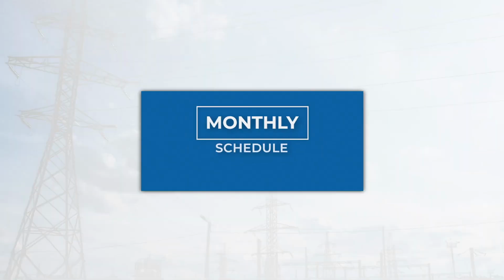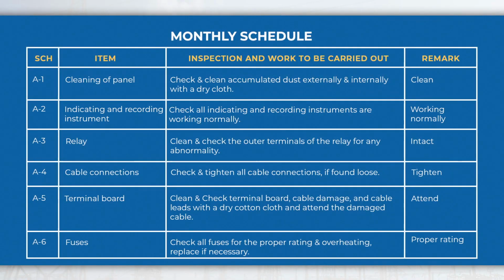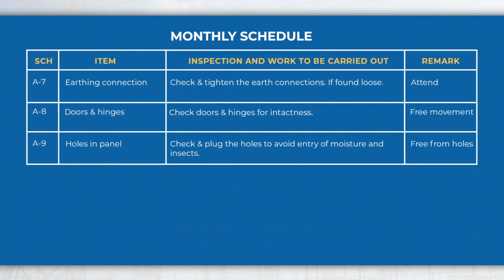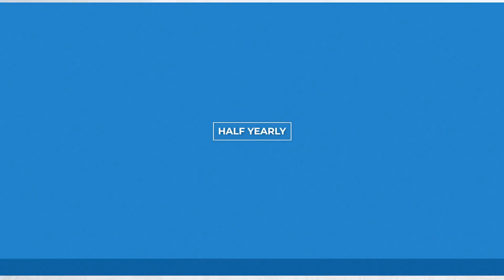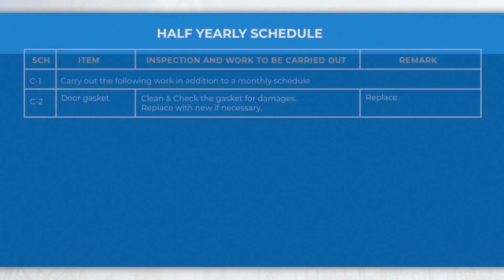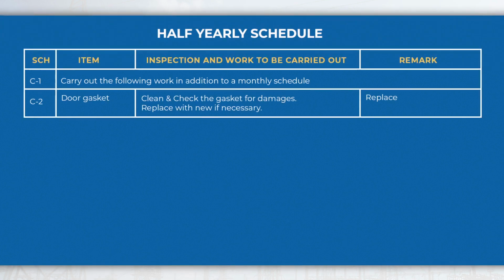Monthly schedule. In the monthly schedule, perform activities like cleaning of accumulated dust, check the indicating and recording instruments, check and clean the outer terminals of relays, check the tightness of cable connections, terminal connections, check the fuses for overheating, earthing connections, and also check the door and hinges for its intactness. Half-yearly schedule. In the half-yearly schedule, perform activities like checking of the door gasket; if found damaged, replace the gaskets, etc. in addition to monthly schedule activities.